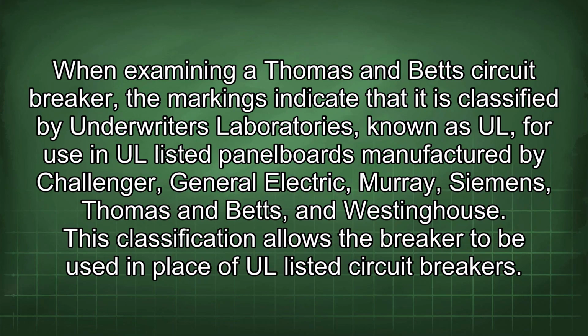When examining a Thomas and Betts circuit breaker, the markings indicate that it is classified by Underwriters Laboratories, known as UL, for use in UL-listed panel boards manufactured by Challenger, General Electric, Murray, Siemens, Thomas and Betts, and Westinghouse. This classification allows the breaker to be used in place of UL-listed circuit breakers.